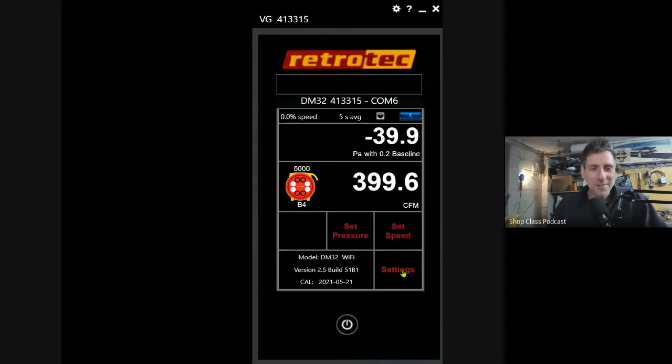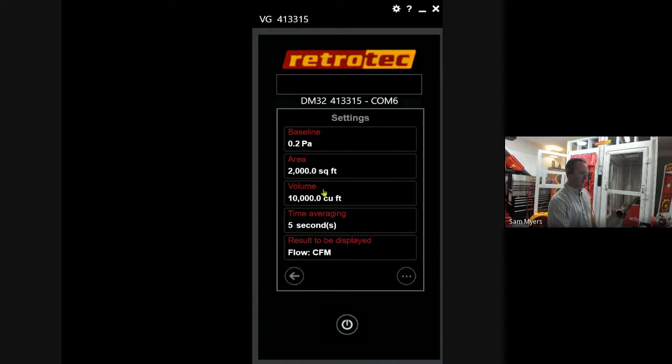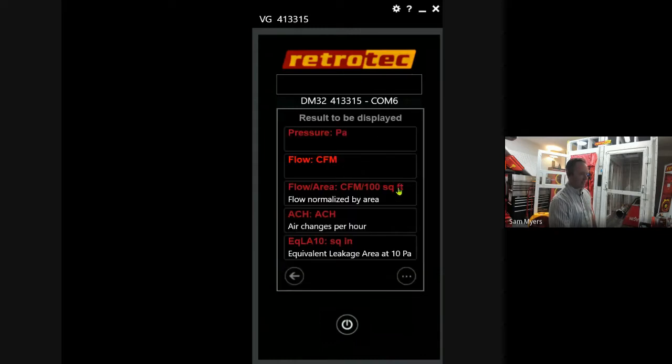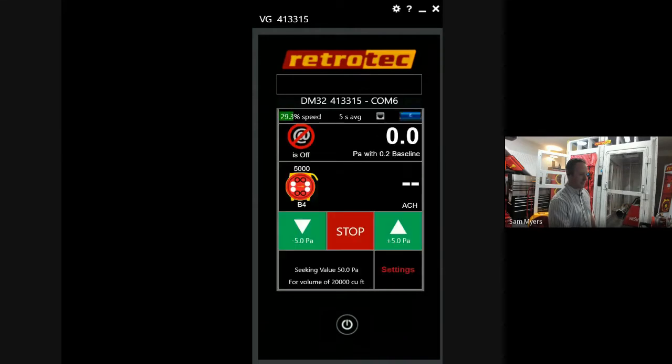I got you. Okay. So turning it off, if I wanted to represent it in air changes per hour, all I'd have to do is enter my volume. So let's just say 20,000 and hit set. And then I can just click on channel B here and select ACH. And then I can just run the test again. So this fictional house would be 1.3, 1.4 maybe, which is not passive house, but that's a pretty good number.